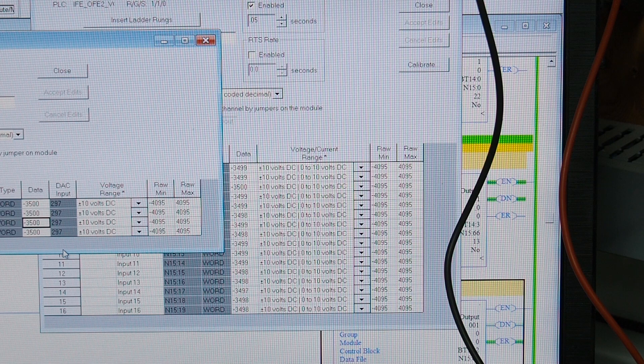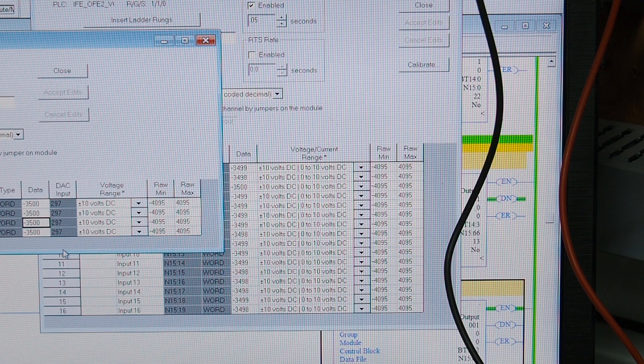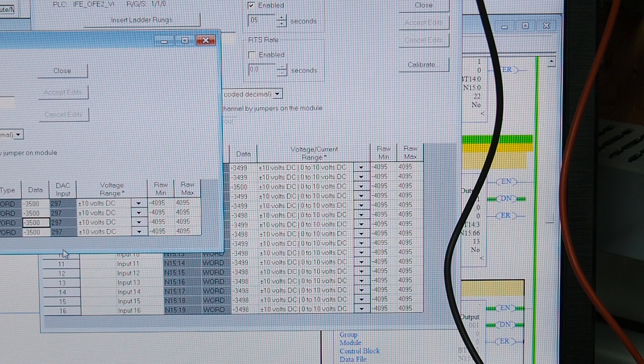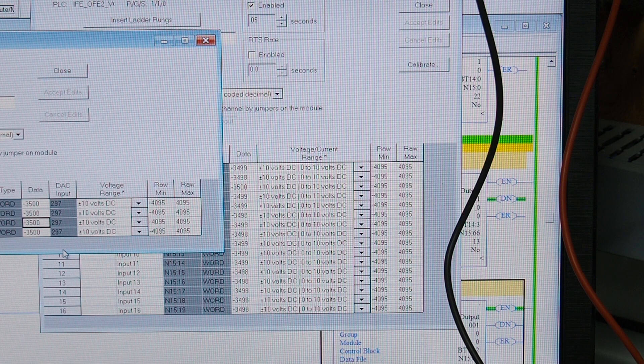The milliamps are exactly the same setup, except we've got two cards on the output, and we do the first group then the second group. And again, I proved it out when I was testing all the cards earlier today, that all of these are plus or minus a couple of digits at the end, and that shows after 23 years that these cards have been out there, these particular cards, they're still working fine.